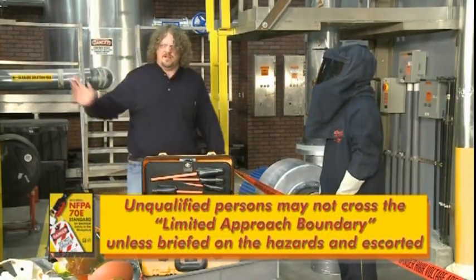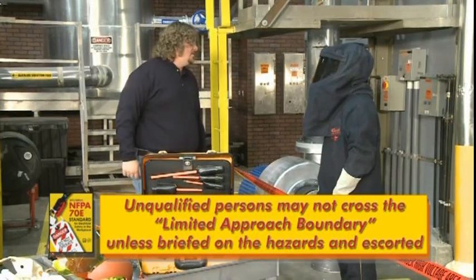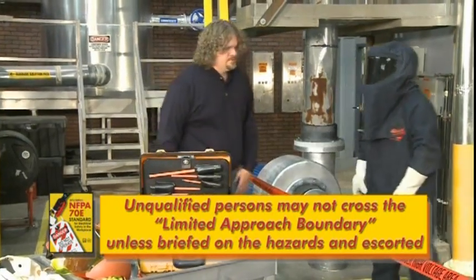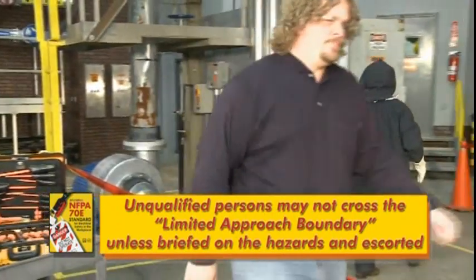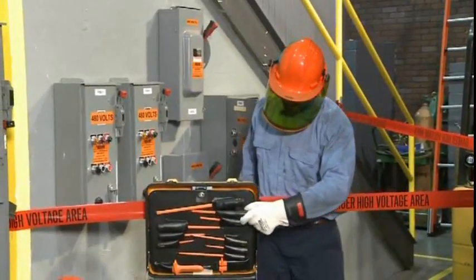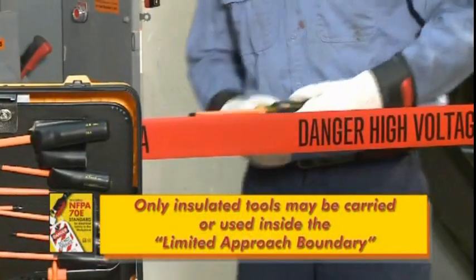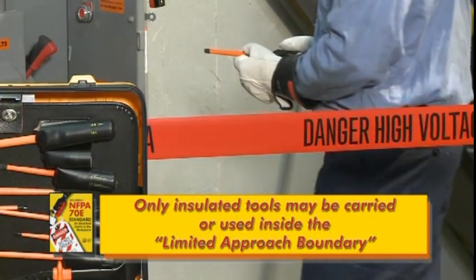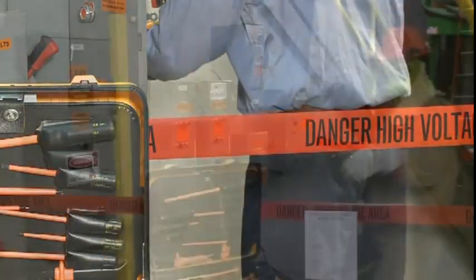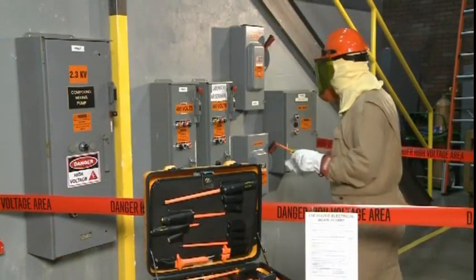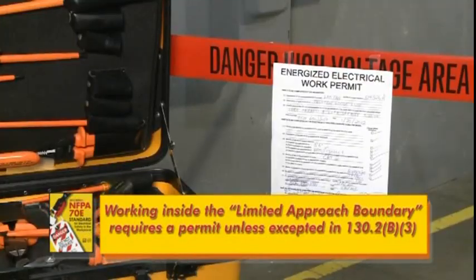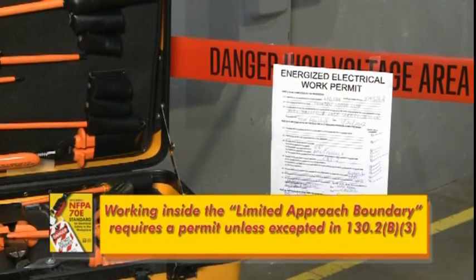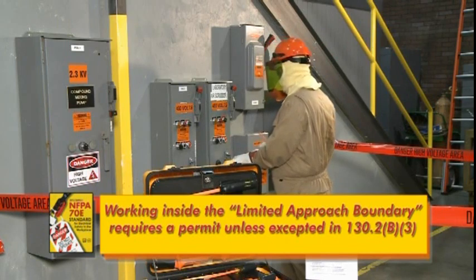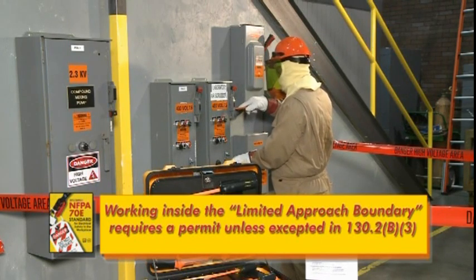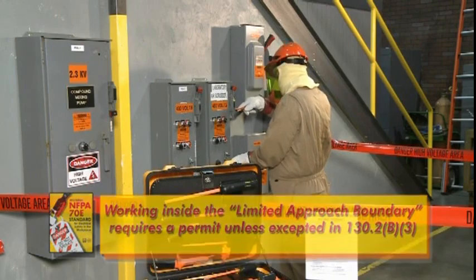Unqualified persons may not cross the limited approach boundary unless briefed on the hazards and escorted by a qualified person. In addition, only insulated tools may be carried or used inside the limited approach boundary. And any live work performed inside the limited approach boundary requires an energized electrical work permit, unless the work performed meets one of the exceptions outlined in 130.2B3.